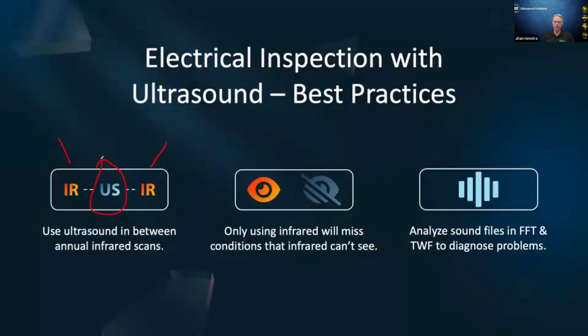And if you're outsourcing infrared thermography to a third party or to your insurance company, use ultrasound in between their annual visits. If you only use infrared, you're going to miss conditions that infrared can't see. And then finally, once you've pulled that ultrasound data in, you have the opportunity to analyze the sound files using both the FFT spectrum and the time waveform to diagnose specific problems.